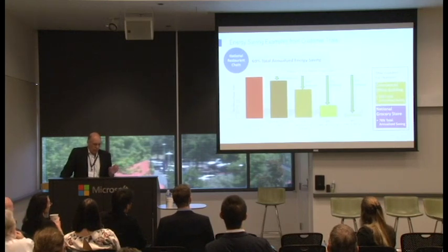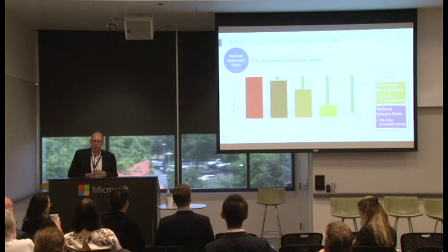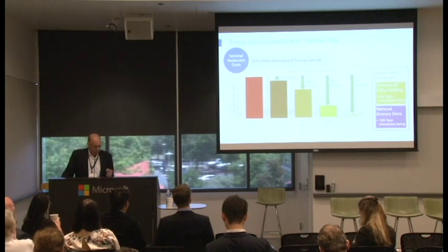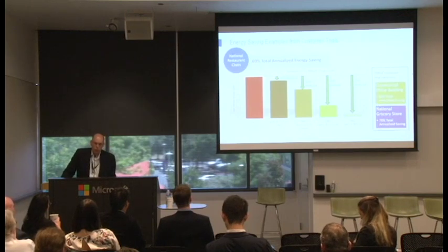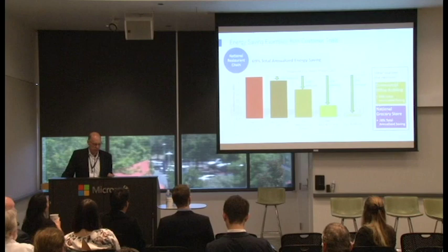So then that's doing a like-for-like comparison. And then what we'll do is, everyone knows in this space that adding variable speed control to a motor can create incremental savings. So we'll add a variable speed control element to that using speed points that are agreed with a customer. And then by that, we can see we can get anything from, in this particular case, a 32% to a 91% reduction in the energy draw of that motor based on the speed it's operating at in the different heating, cooling, or ventilation modes of that system.